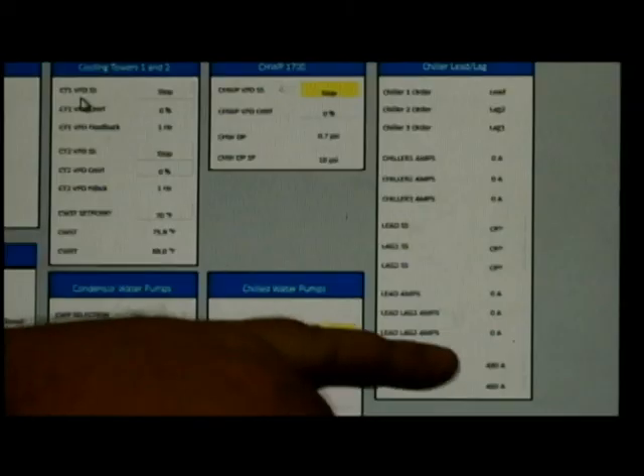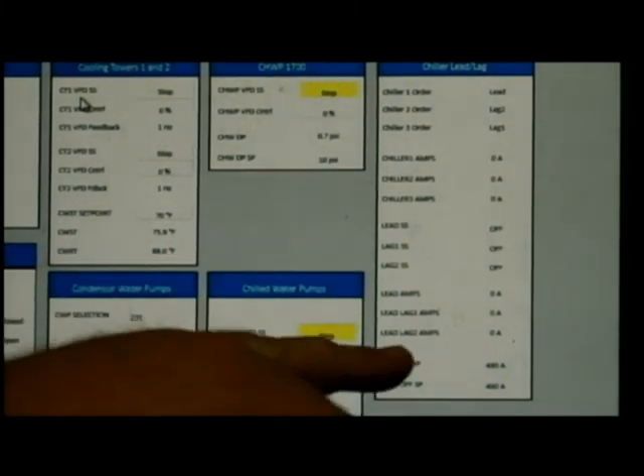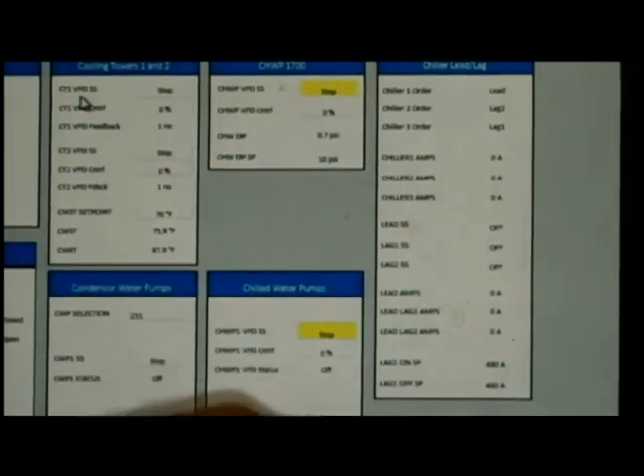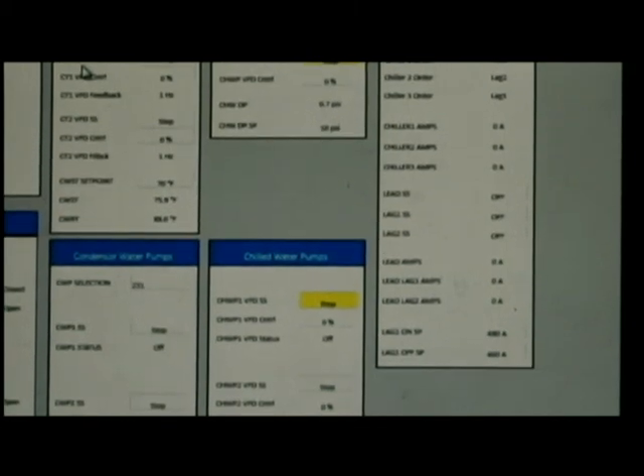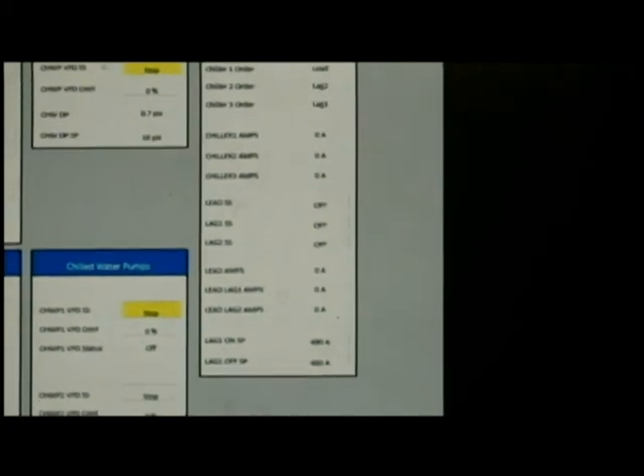Just below that, we get into the lead lag and lag one and lag two amps. In order to monitor the system, not the same chiller is always lead and not the same chiller is always lag. So we take a combination of whatever chiller is lead and plug in its amps for the lead amp. So that is the lead chiller. Whichever chiller is running lead, its amps will report right there. For the lag, same thing, report in lag two.